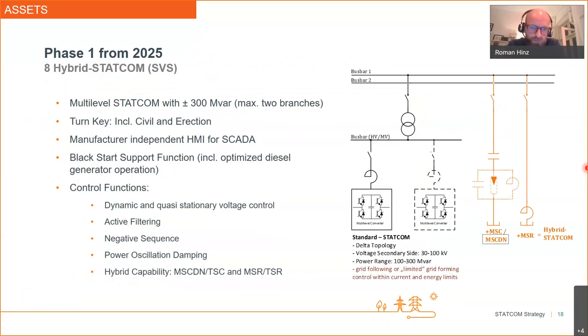Our plan is for the first stage, as Cornelius said, to tender for in total 8 STATCOMs together, operated with MSCDN or maybe with an MSR. MSR is a mechanical switched reactor and MSCDN is a mechanically switched capacitor with damping network. And here for us right now, we had to face a little bit more the real world, because when we went to the manufacturers 2 years ago and we asked for this kind of grid forming behavior, the manufacturers were a little bit surprised about this demand. Maybe they heard about it, but for STATCOM, it was quite new for them.